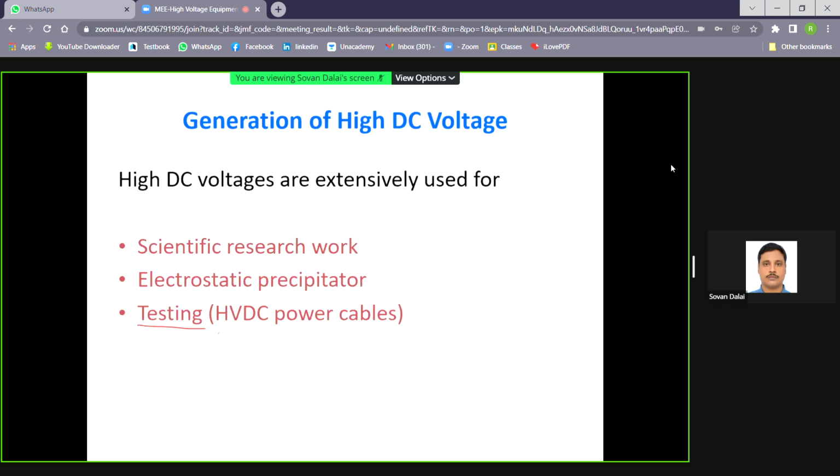Why is the design of power cable restricted to a certain voltage level? The maximum you can see is 132 kilovolt for underground cable, but overhead transmission lines are designed in the range of 1000 kilovolt to 1200 kilovolt. For the same reason, when we test a power cable with high voltage AC, it requires a large amount of charging current from the source. To avoid that, power cables are generally tested with HVDC.